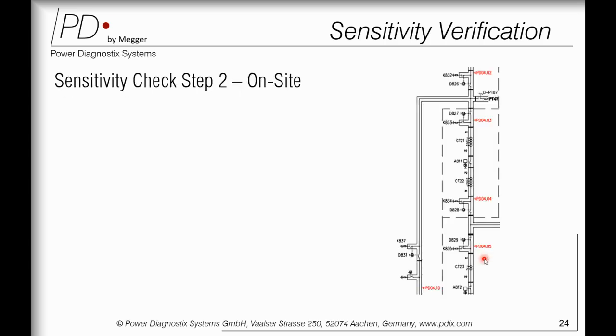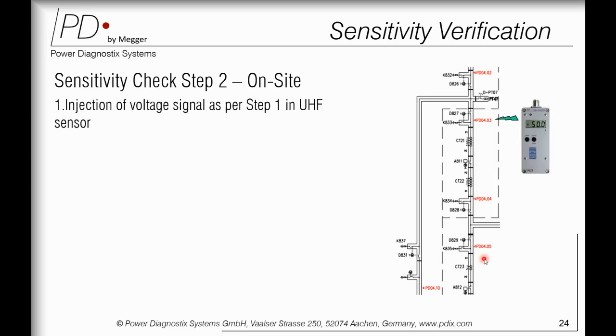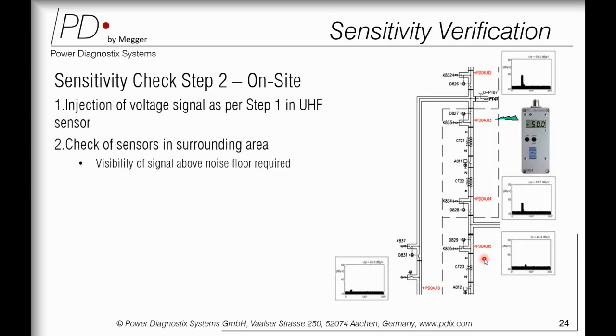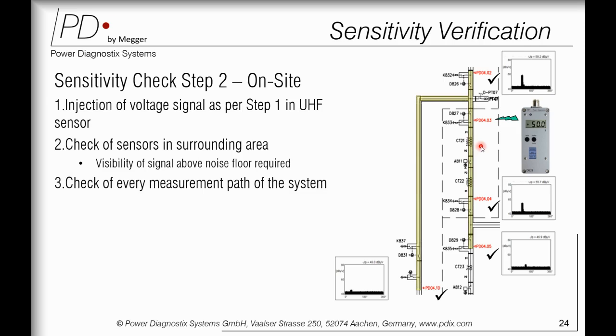Then for on-site measurements, you use the same pulse injector, inject that voltage in your GIS, and make sure the sensors installed in your GIS are more than sufficient and capture signals equivalent to 5 pC. So I have injected some pulse here, and the electromagnetic waves travel from here to here. It will capture here, and it also passes here.